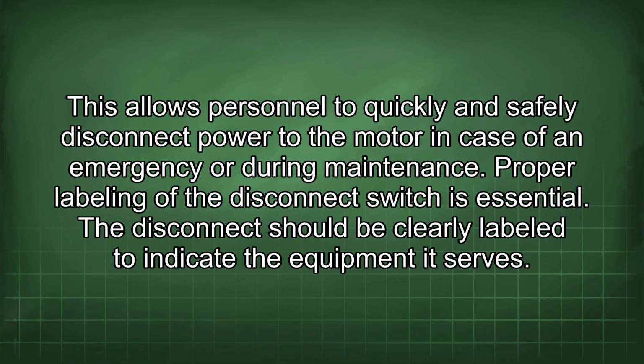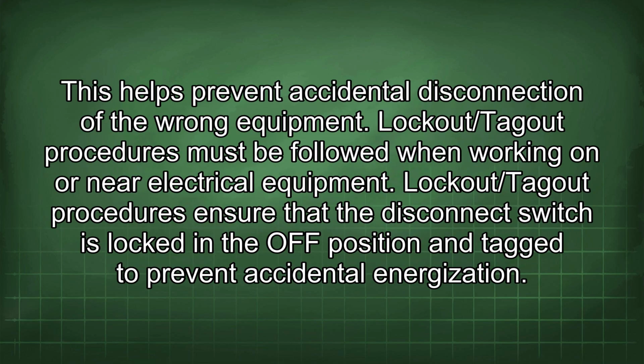Proper labeling of the disconnect switch is essential. The disconnect should be clearly labeled to indicate the equipment it serves. This helps prevent accidental disconnection of the wrong equipment. Lockout/tagout procedures must be followed when working on or near electrical equipment. Lockout/tagout procedures ensure that the disconnect switch is locked in the OFF position and tagged to prevent accidental energization.